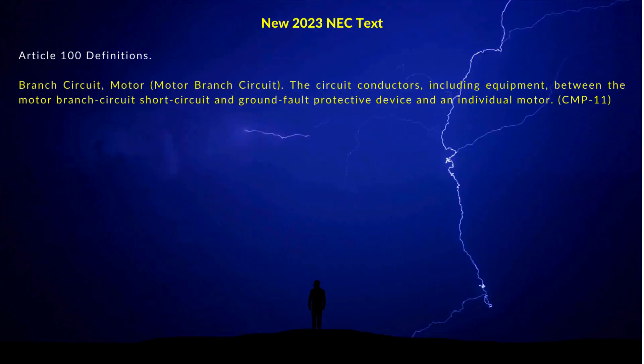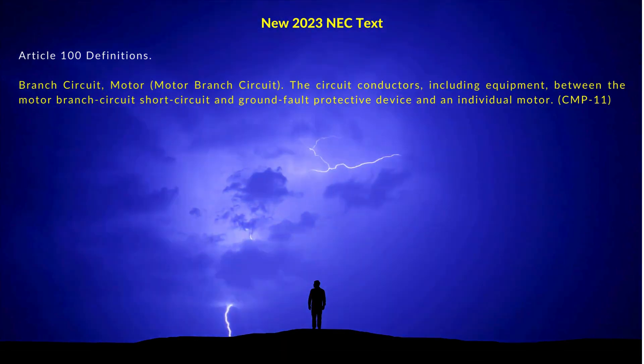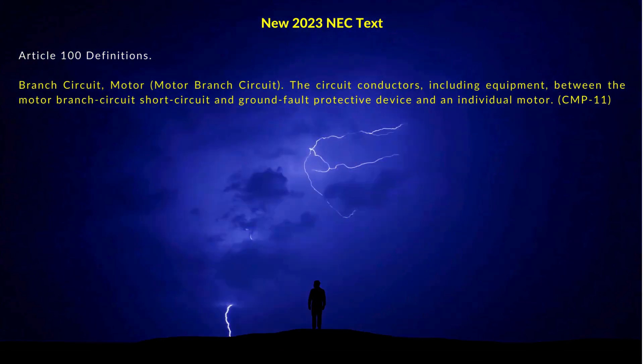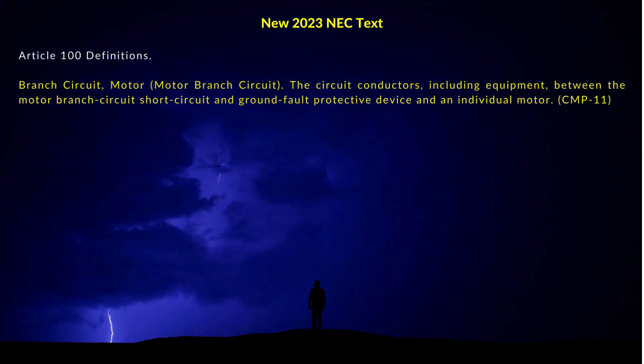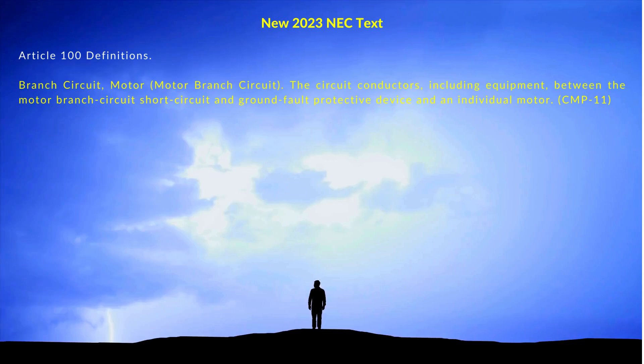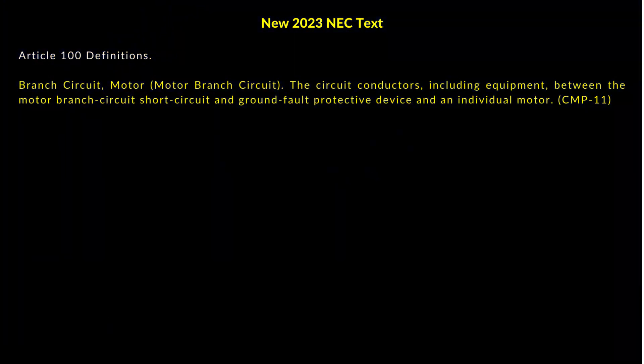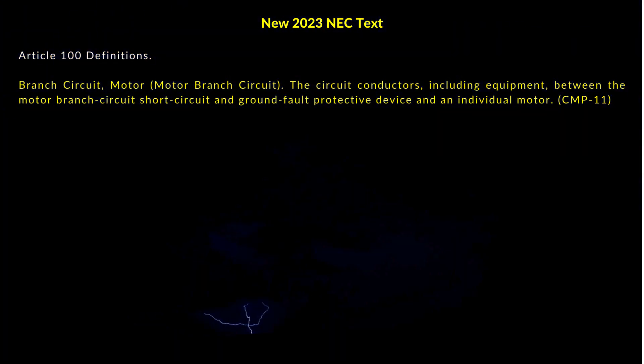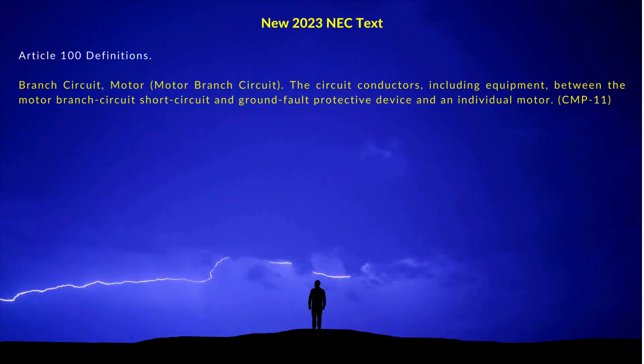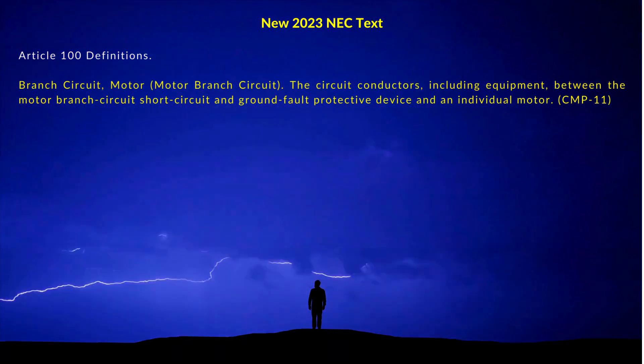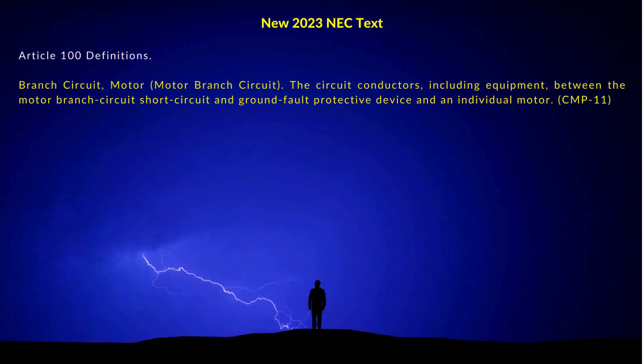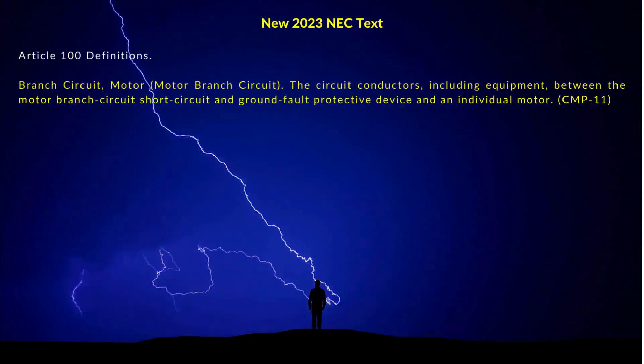The new 2023 NEC text for branch circuit motor states that the circuit conductors, including equipment, between the motor branch circuit short circuit and ground fault protective device and an individual motor.